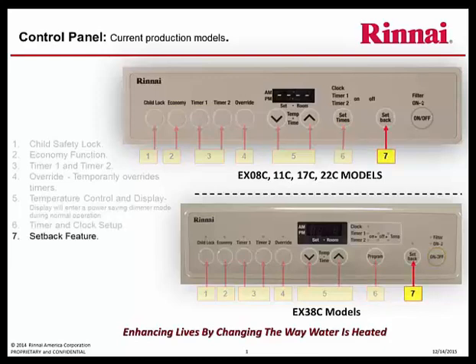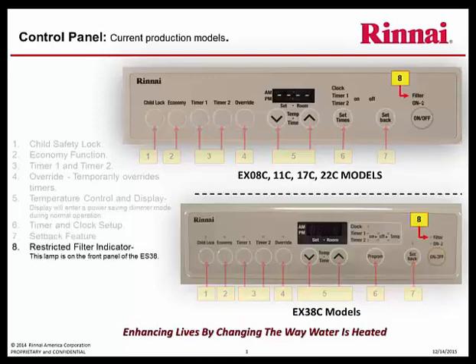Setback feature: this allows for energy savings when no one is present in the structure, or can be used as a frost protection feature. Restricted filter indicator lets you know that not enough air flow is passing through its cabinet, which is generally an indication that the air filter has become clogged.